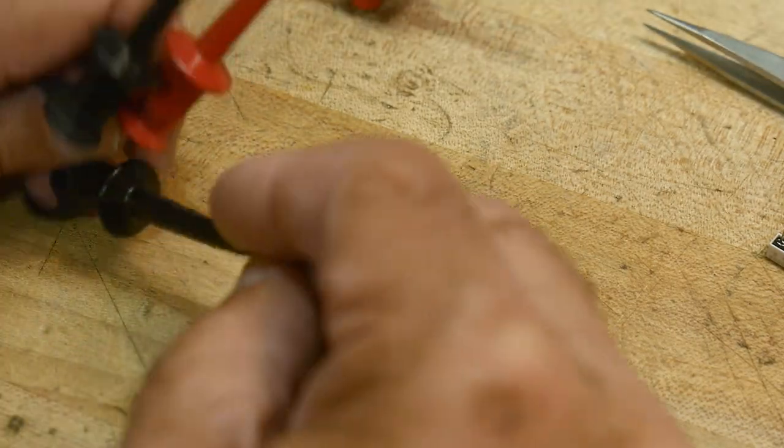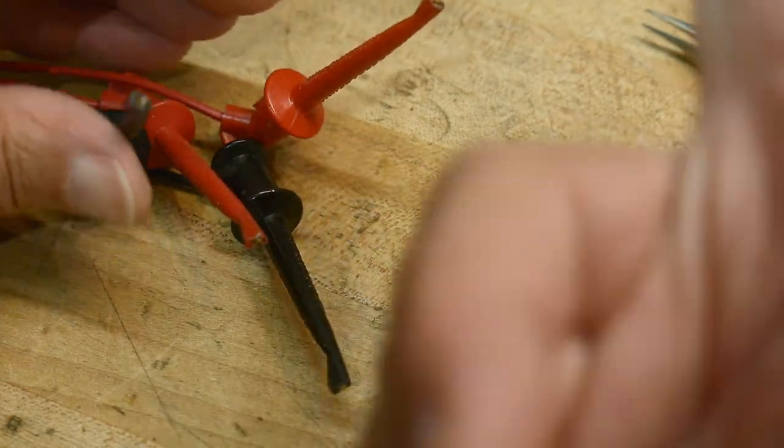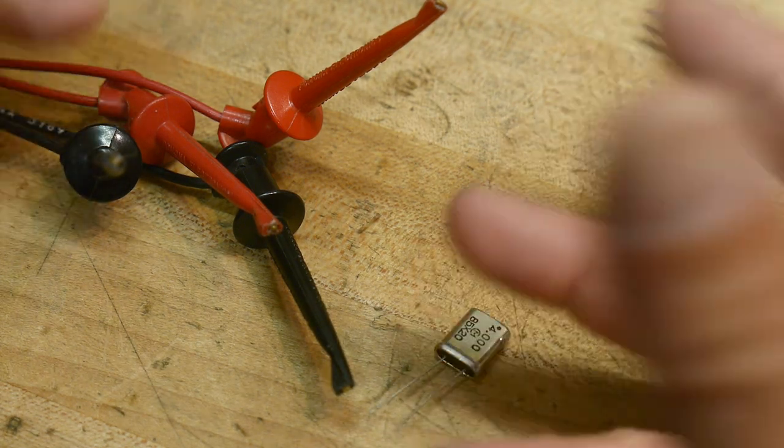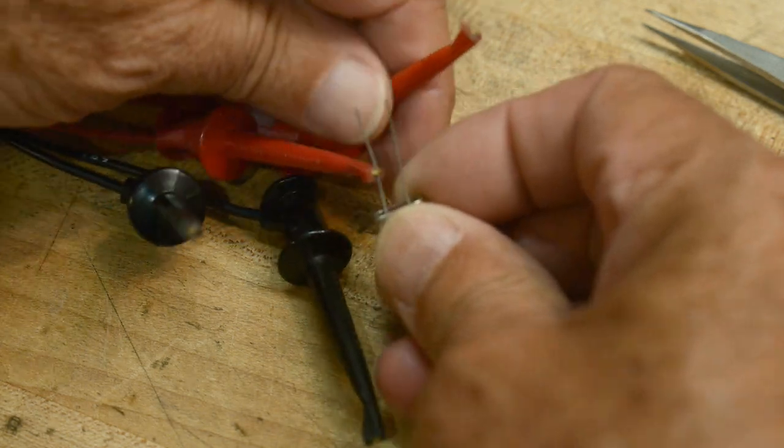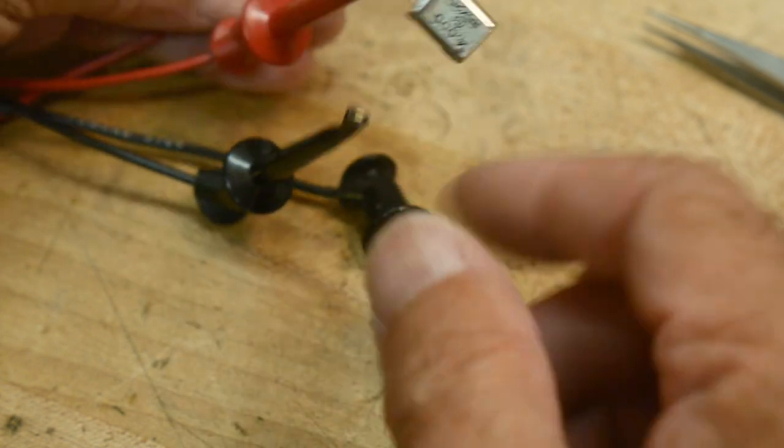You could use your nano VNA, you could put it in S21 mode, or you can use a spectrum analyzer with a tracking generator. That's what we're going to do. We are going to sweep this. We're just going to put our clip leads right across it, no need to hook up the ground. We'll just put it that way.